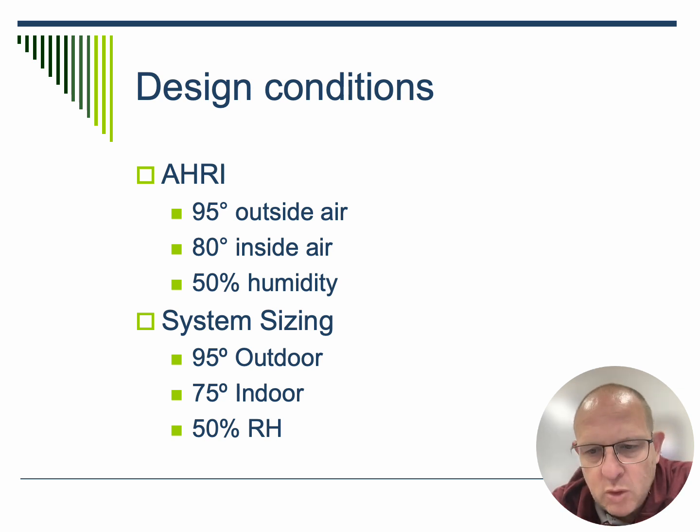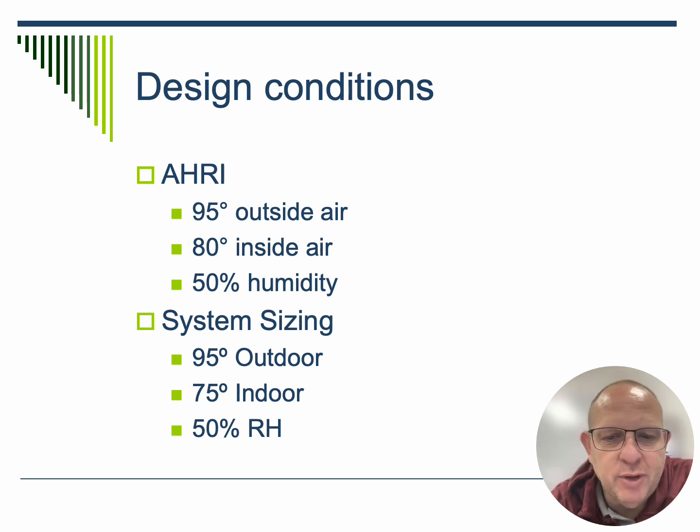Now, when we are dealing with the comfort of individuals, 80 degrees is a really warm temperature for us to run our houses at. So what we want to do is design these systems to run at a 95-degree outdoor temperature, 75-degree indoor temperature, with a 50% relative humidity value.